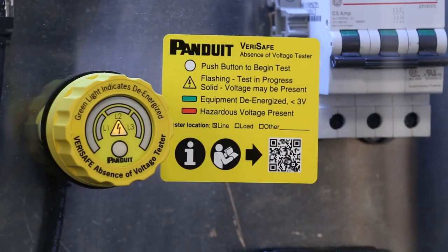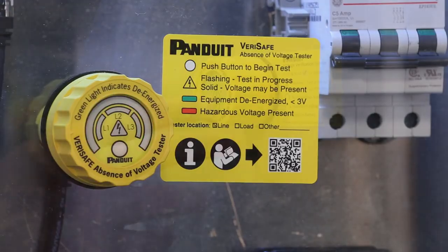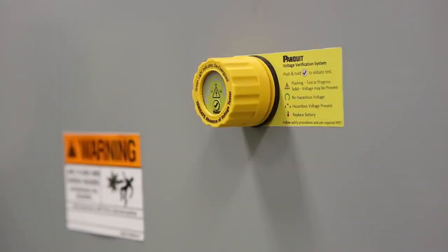At this point, the device is performing a self-test, verifying installation, checking for any AC or DC voltage on the system, phase to phase, phase to ground, on all phases.